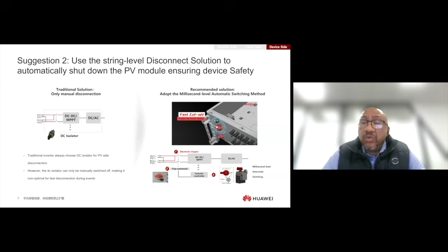Secondly, we are suggesting using string-level disconnect solutions. Typically you would have the DC isolator employed to isolate the PV side during fault events. However, this DC isolator is typically manually switched off, making it non-optimal for fast disconnection during events. What is being proposed is the use of an inverter controller as well as a fast cutoff switch that can be deployed within milliseconds, thereby enhancing safety not only of the device but, of course, for human interaction as well.